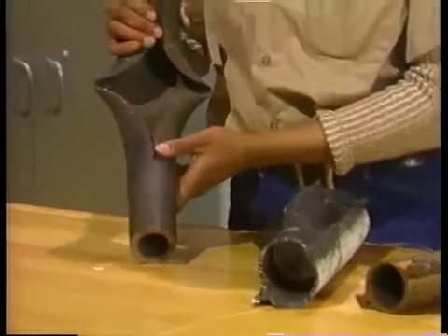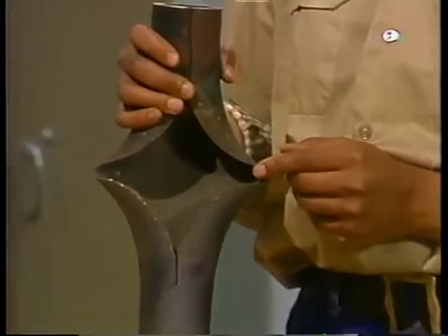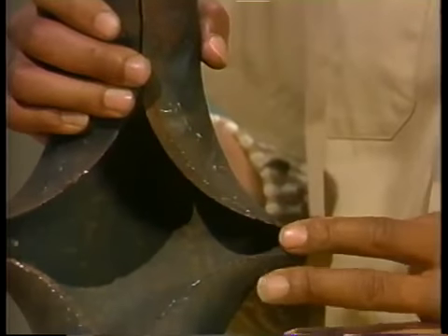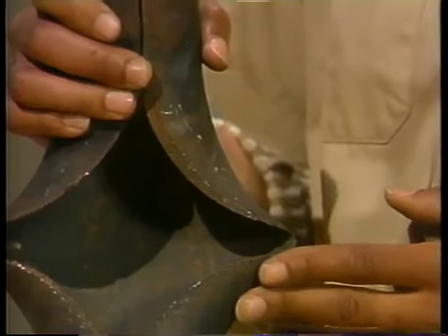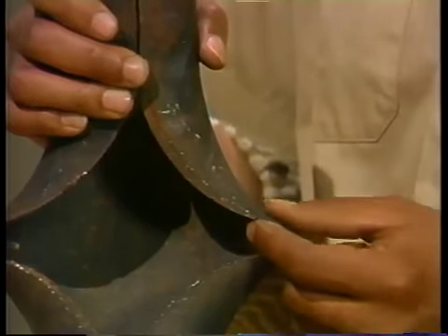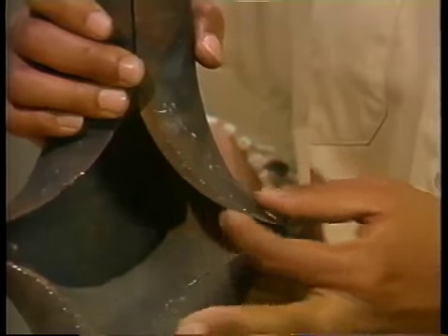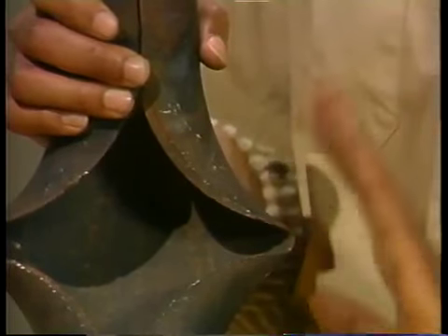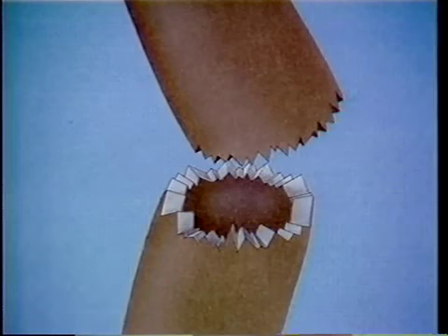Now, thick-lipped ruptures are caused by milder but more prolonged overheating. This kind of overheating is often caused by deposits on the inside of the tube. Thick-lipped ruptures resemble thin-lipped ruptures, except that their edges are thicker and more ragged, as you can see here. This kind of rupture is common to superheater tubes. Double-end ruptures are also caused by overheating. Here, the tube separates completely at the point of failure, leaving two free ends.